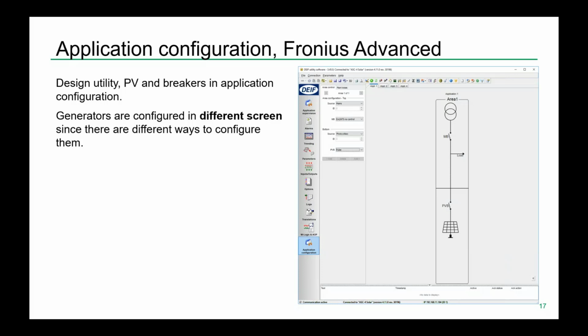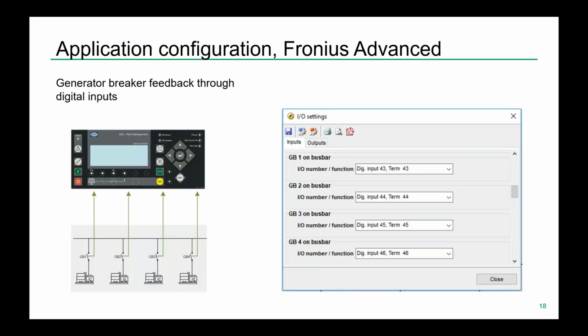On the advanced solution, since it is not a fully integrated solution, you can't see the generators here. This is configured on a different screen, so it looks like this. If you have 4 generators, as the example shows, then you will simply go into the I/O settings and decide where you want to connect the breaker position feedback. So in this case, it's on terminal 43, 44, 45, and 46. So with these inputs, we'll tell the ASC now generator 1 is connected, or 2, 3, or 4. So it is doable, definitely.